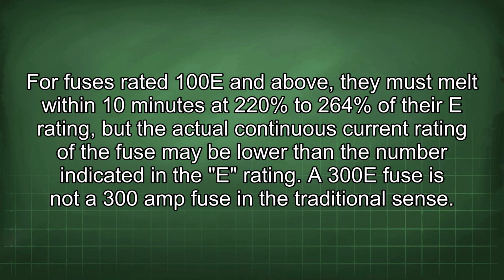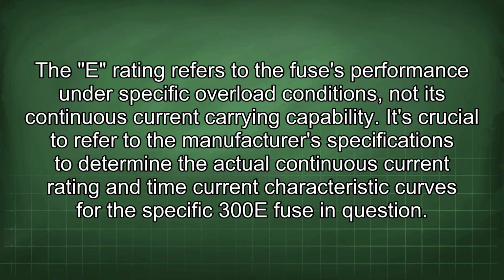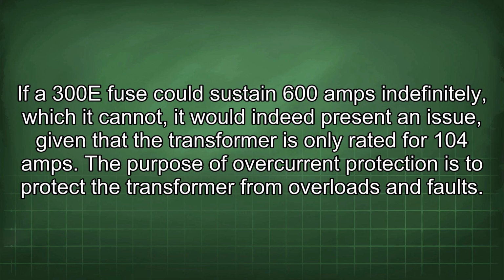A 300E fuse is not a 300 amp fuse in the traditional sense. The E rating refers to the fuse's performance under specific overload conditions, not its continuous current carrying capability. It's crucial to refer to the manufacturer's specifications to determine the actual continuous current rating and time current characteristic curves for the specific 300E fuse in question. If a 300E fuse could sustain 600 amps indefinitely, which it cannot, it would indeed present an issue, given that the transformer is only rated for 104 amps.